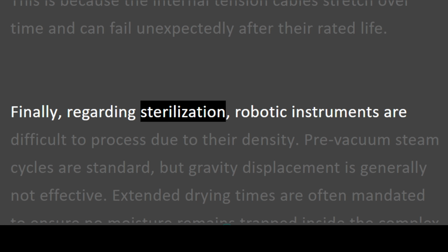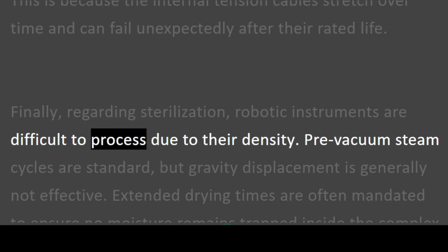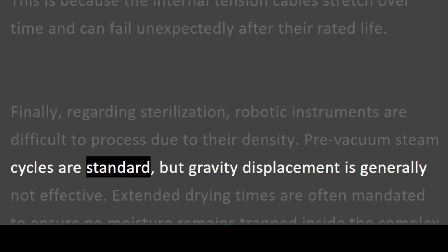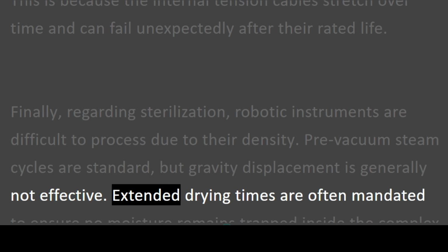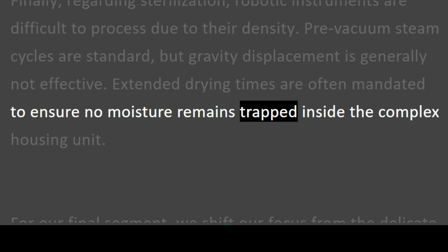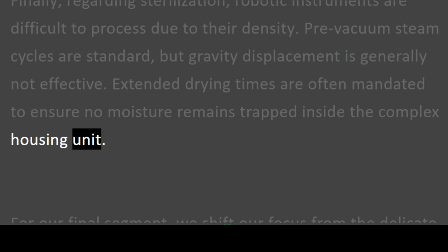This is because the internal tension cables stretch over time and can fail unexpectedly after their rated life. Finally, regarding sterilization, robotic instruments are difficult to process due to their density. Pre-vacuum steam cycles are standard, but gravity displacement is generally not effective. Extended drying times are often mandated to ensure no moisture remains trapped inside the complex housing unit.